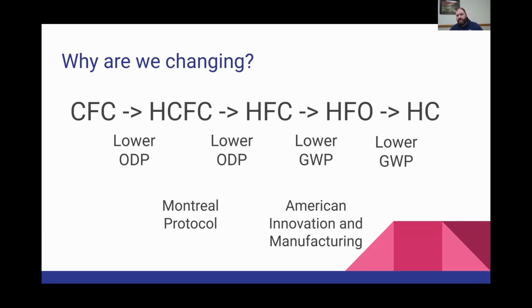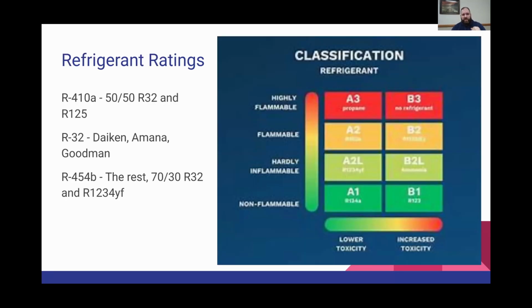And we're moving towards HFOs and HCs. HFOs are hydrofluoroolefins, and HCs are hydrocarbons. Hydrocarbons are our lowest GWP refrigerant, and we'll talk about where some confusion comes in. All refrigerants, and I apologize that this isn't as clear as it could be, are rated on this classification scale. The first column is column A, and those are A refrigerants. They are lower toxicity refrigerants. The right-hand column, column B, is increased toxicity. Pretty much all the refrigerants I've mentioned up to this moment have been classified as A1s. So R11, 12, 22, 410A, 134A, 407C, they're all A1 refrigerants.